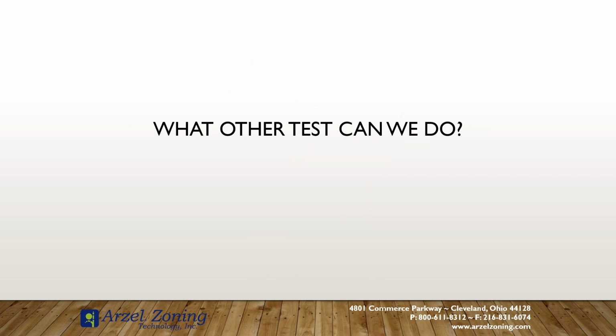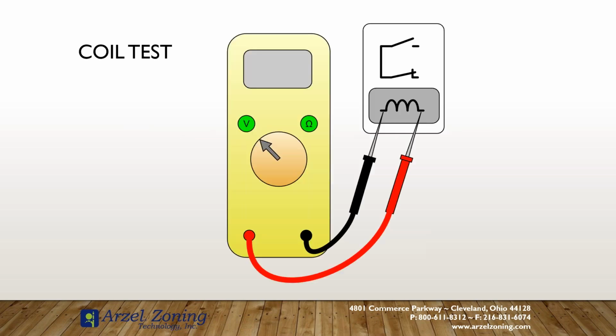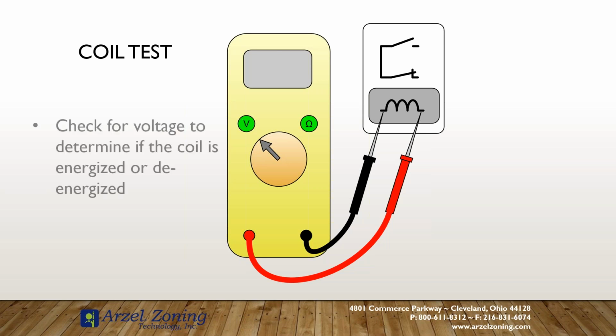But sometimes we can't always test for ohms. So in those cases, we need to test for voltage. Now when I'm testing for voltage, my coil, if it's reading 0, indicates that it's not engaging my relay. So if I test my coil and I have 0 volts across my coil on that relay, I'll know that the control source is not calling for that relay to operate. If I read 24 volts on that coil, then I know that that coil or that relay is supposed to be energized.